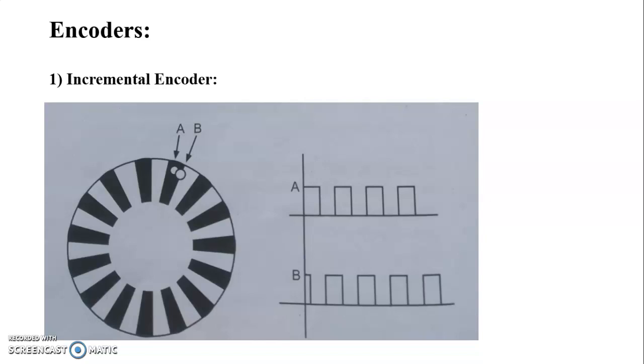However, friends, this method has some serious disadvantages. It is possible that the result is continuously invalid due to signal glitches, unmeasured impulses, or similar problems. Furthermore, after a loss of the supply voltage, it is often necessary to return to the reference point, which can be a complication. For this reason, applications with a high emphasis on precision, or applications where it is complicated or not possible to return to the reference point, often use the absolute measuring system.